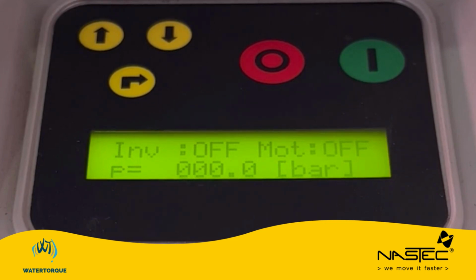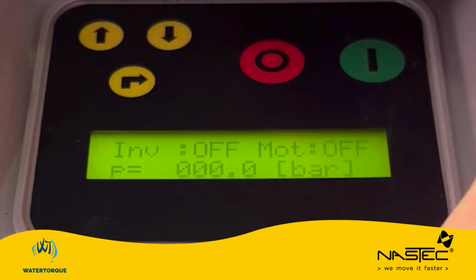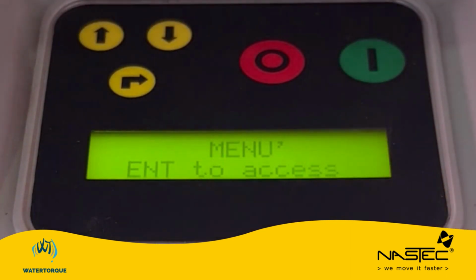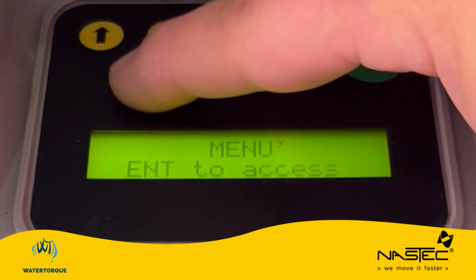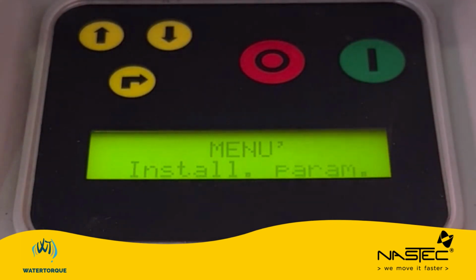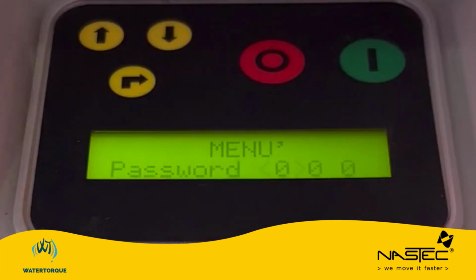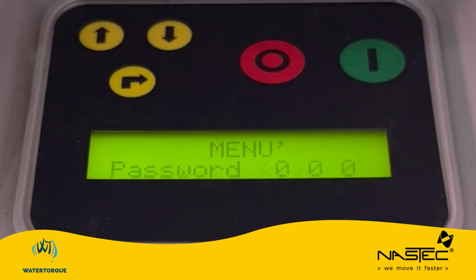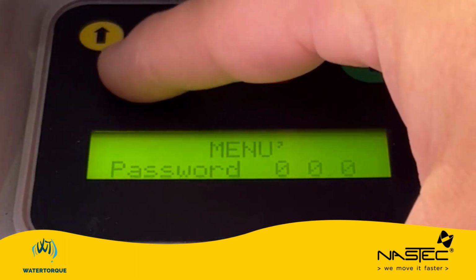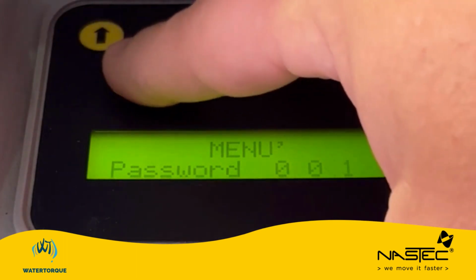Next thing we need to do is access the installation parameters. What we do there is we hit the up arrow, which is menu, enter to access. So we hit the enter button. Now we can see install parameters. We need to hit the enter button again, and the password is 001. The way that we do that is we hit enter, enter, up, and enter.